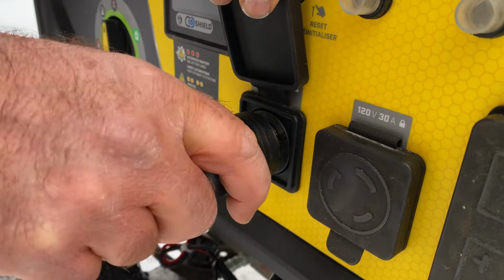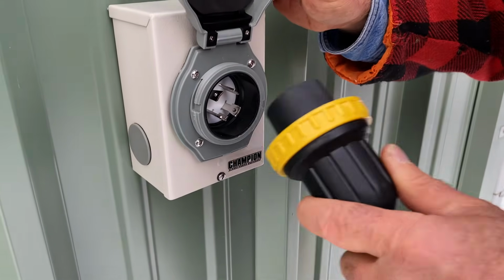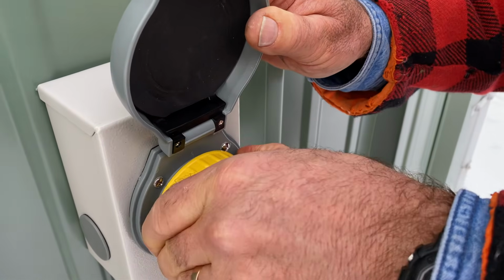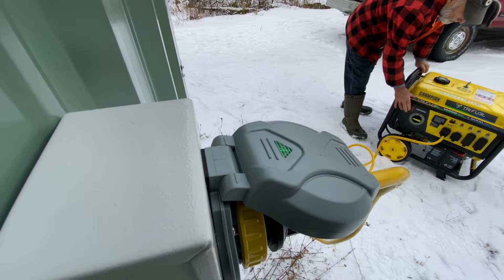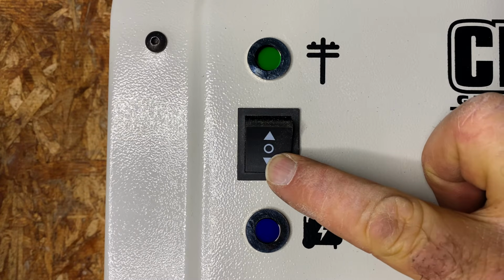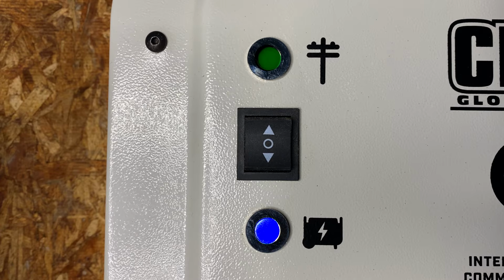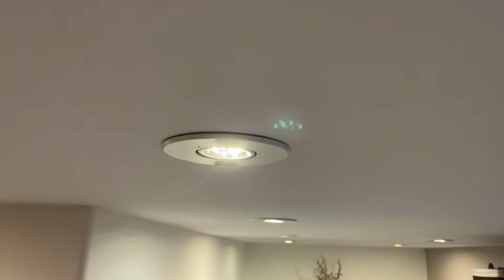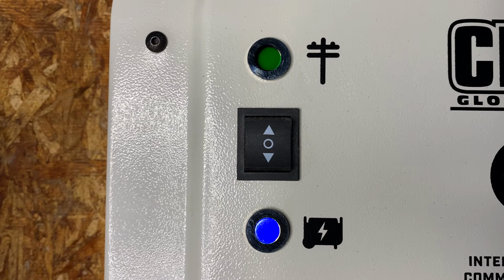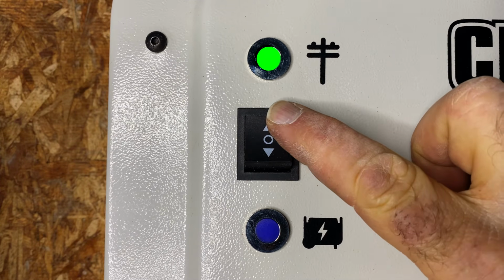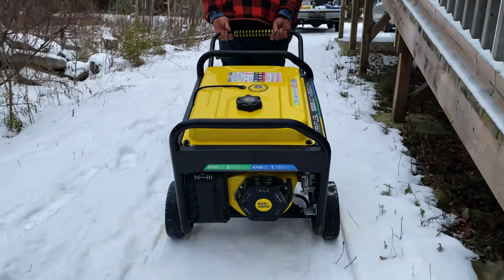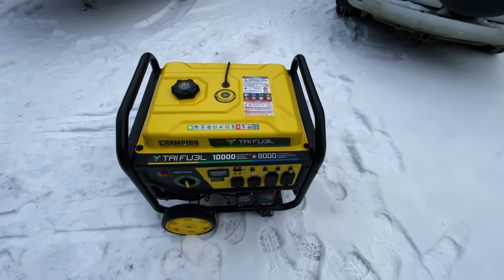When grid power goes down, you need to do two things. One, connect your generator to the weatherproof outlet using the special power cord provided with the unit. Then get the generator running. Two, flip on the manual transfer switch inside your home to disconnect the panel from the grid. This simultaneously establishes a direct connection between your generator and those essential circuits you had rerouted into the transfer switch panel, all with a guaranteed disconnection from the grid. Both functions are handled by the same two-position toggle switch.